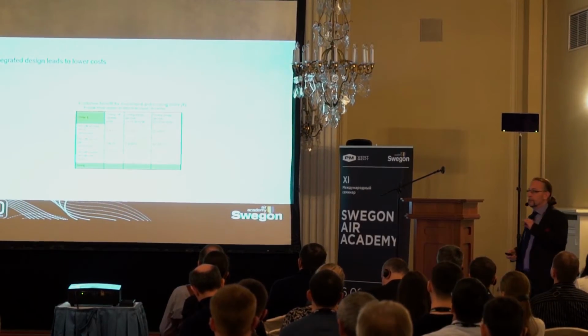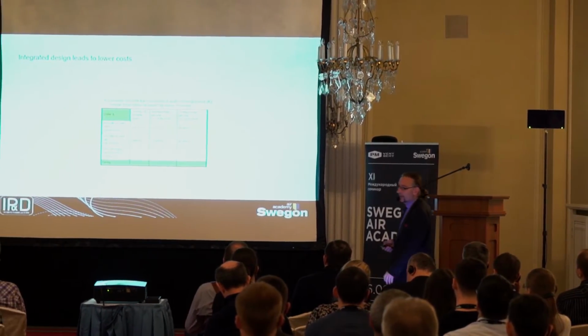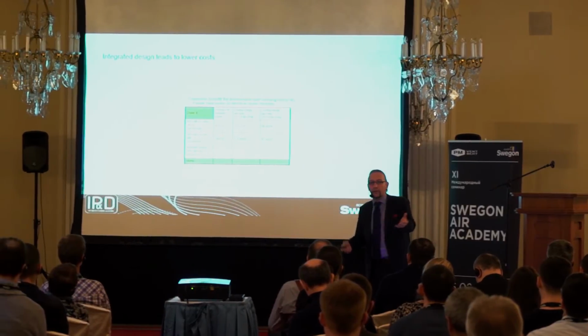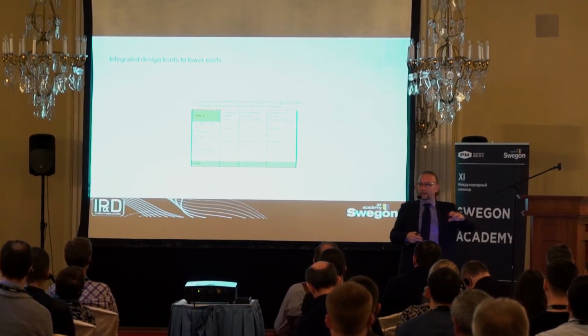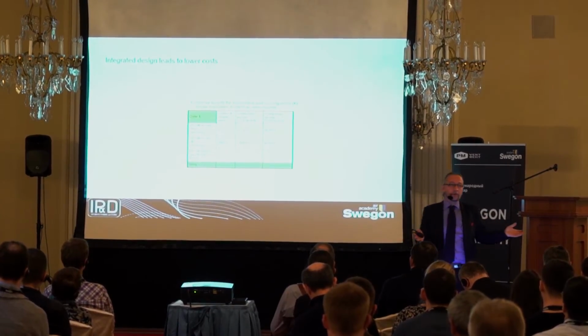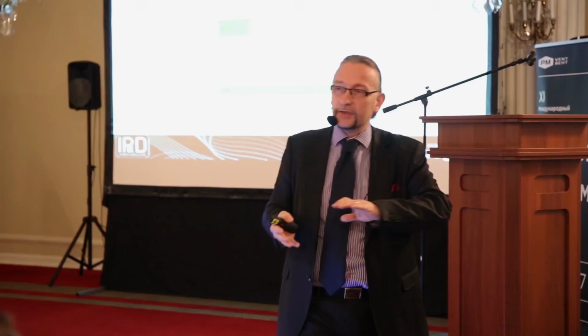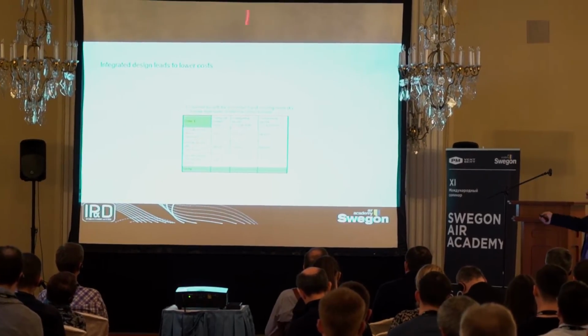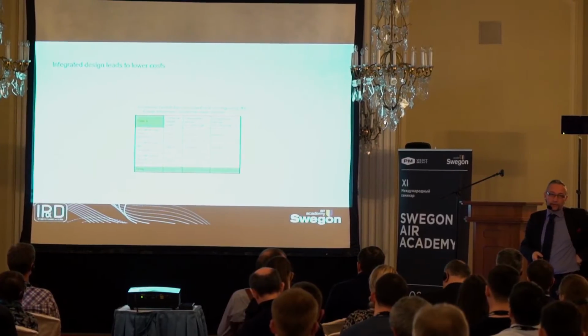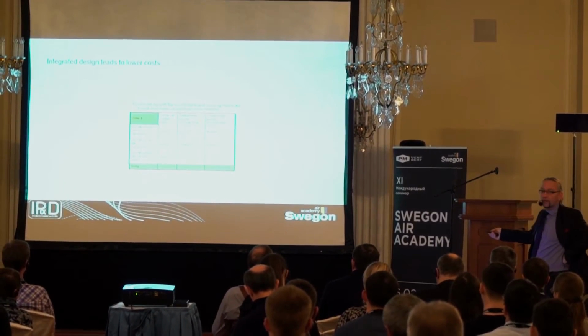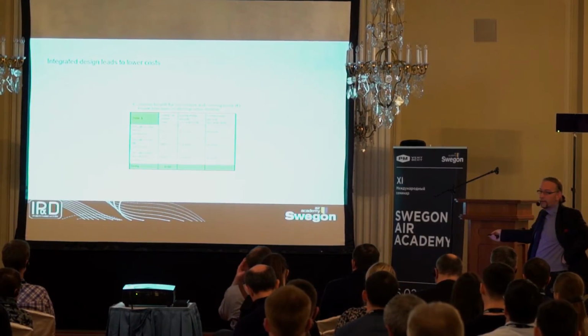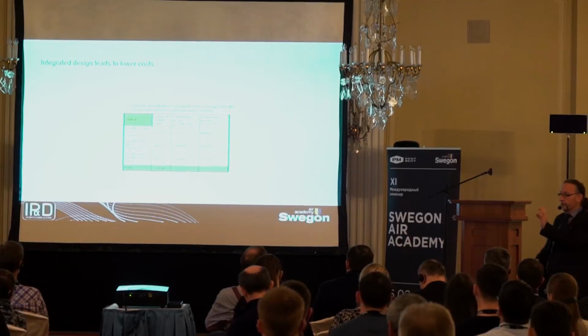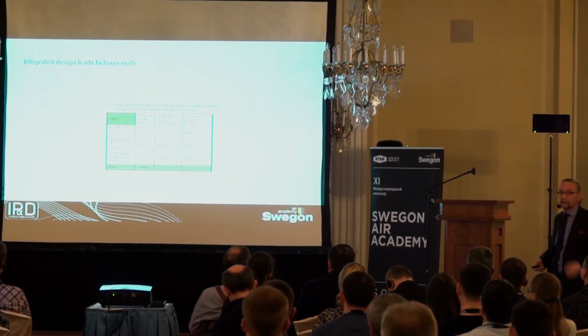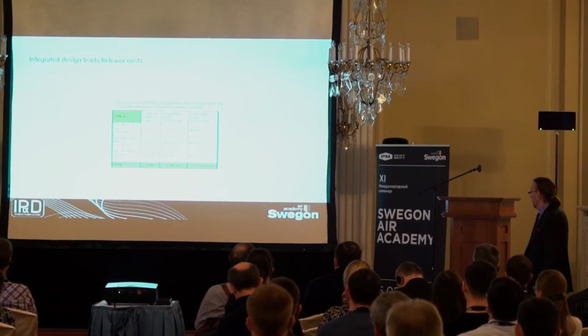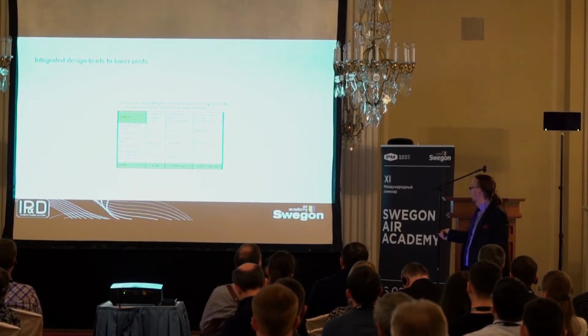Now you add the sorption rotor, and the sorption rotor costs you, I don't know, Sergei, a couple of rubles in comparison. It's nothing. The sorption rotor will recover the humidity. In places like Krasnodar, extremely interesting. We're talking about 30% saving. St. Petersburg, it's around 8% saving. But here in Rome, you're down to 199 kilowatt installed cooling power, which means half the size of the chiller. So this is a direct saving of 25,000 euros just on the chiller for a sorption rotor that costs you a couple of hundred or a couple of thousand rubles. It's quite interesting. And of course, the running cost, as you see here, it's up to 17,000 euros cheaper per year on top of that.